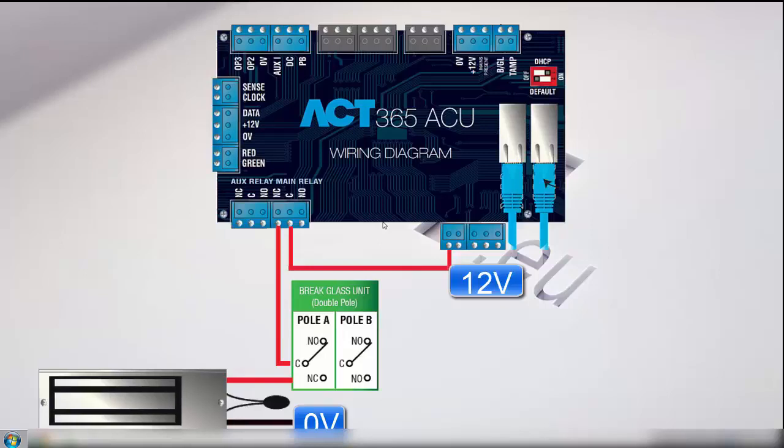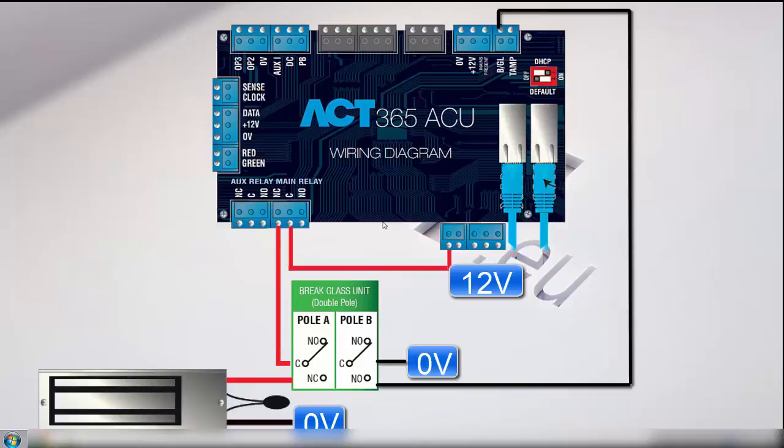To wire we need to bring zero volts into the common terminal of the break glass and then coming out of the normally closed we need to bring this around and wire it into break glass detection input. And that's all that is required to wire the break glass detection.